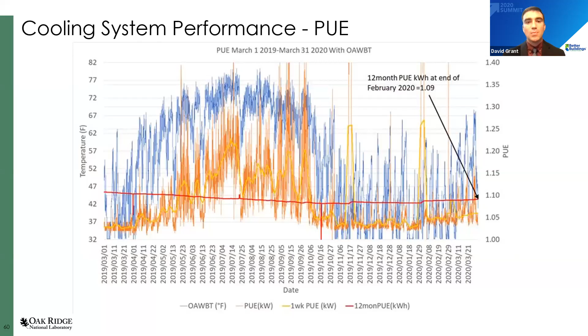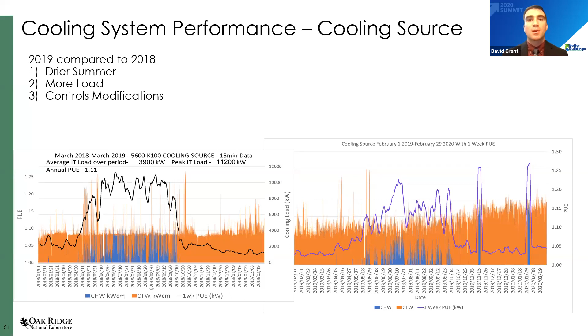So these show some additional benefits or improvements that we've made between the summer of 2018 and 2019. These are individual pieces of data that are stacked columns. The orange represents the load that is on the cooling tower, and the blue represents the load that is on the chill water system. And they're stacked on top of each other to show you total load. And so you can see between the 2018 and 19, there's less blue in the 2019. And that's for several reasons. We did have a drier summer, and you can see that the total load or utilization of the system went up over time. And we also made controls modifications, such as resetting the supply temperature up a degree, that also enabled more economization than the summer before.